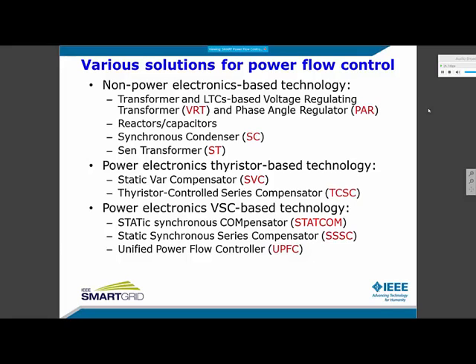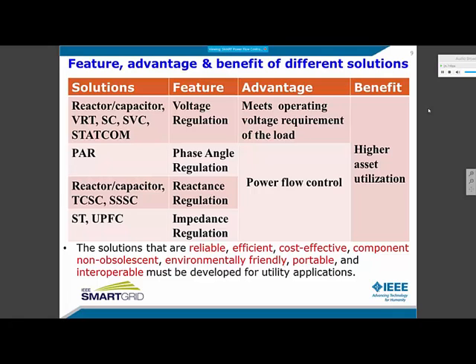If we examine the features of all these controllers and their advantages and benefits, we find that one set of controllers offers voltage regulation that meets the operating voltage requirement of the load. A PAR offers the phase angle regulation. Another set of controllers offers reactance regulation, and the UPFC offers impedance regulation. These features have the advantage of controlling the power flow in the line and ultimately a higher asset utilization for the utility. The cost and complexity of these solutions vary widely. I think that a solution that is reliable, efficient, cost-effective, component non-obsolescent, environmentally friendly, portable, and interoperable must be developed for utility applications.